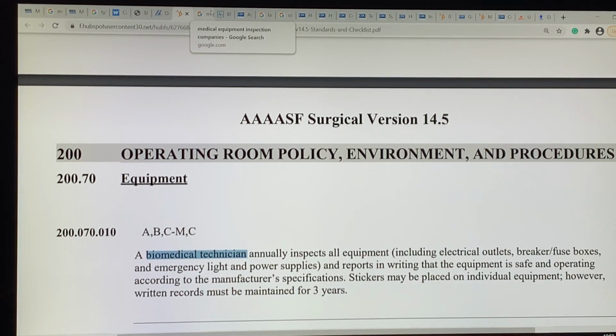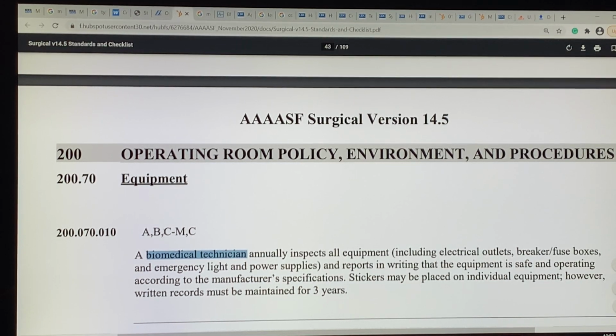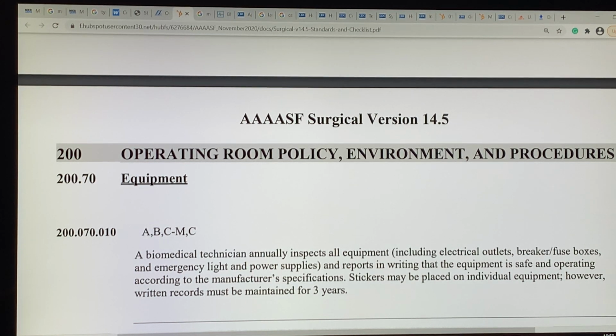Section 200.70, equipment. A biomedical technician annually inspects all equipment, including electrical outlets, breaker, fuse boxes, and emergency light and power supplies, and reports in writing that the equipment is safe and operating according to the manufacturer's specifications. Stickers may be placed on individual equipment, however, written records must be maintained for 3 years.